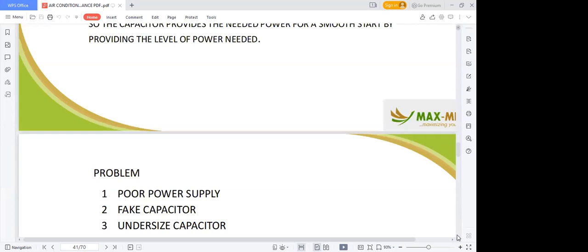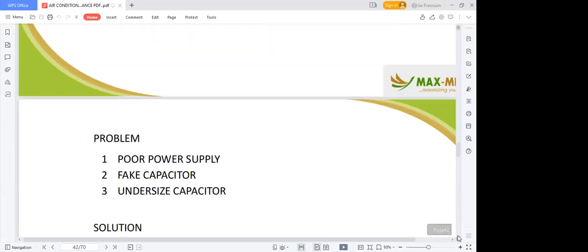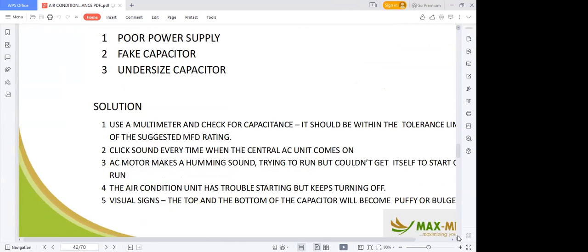Then the problems for the capacitor: poor power supply will not make them function well. There are some fake capacitors, low standard, that are also in the market. Then an undersized capacitor: if your capacitor is to have 50 microfarad and you put in 30 microfarad, you are doing more harm to your compressor. So you buy the required size. Solution: use a multimeter and check for capacitance.